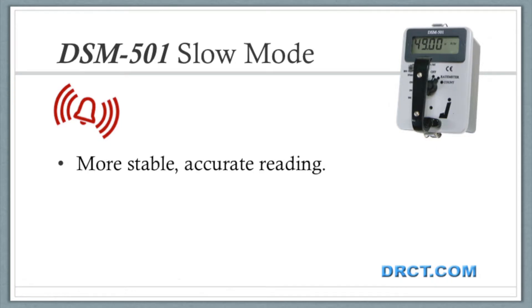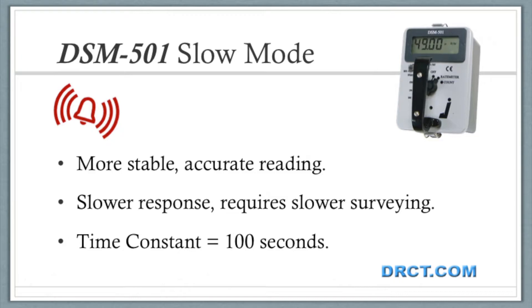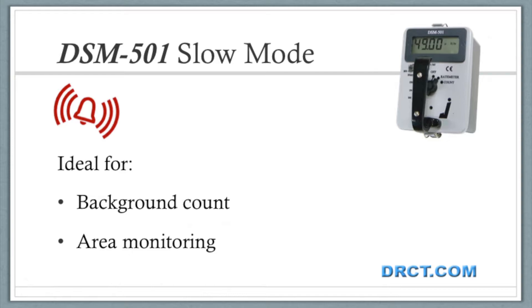Utilizing the slow mode will result in a more stable accurate reading, but it will require the operator to scan the area of interest at a much slower rate. For slow mode, the time constant is 100 seconds. This mode is more ideal for area monitoring or a background count.